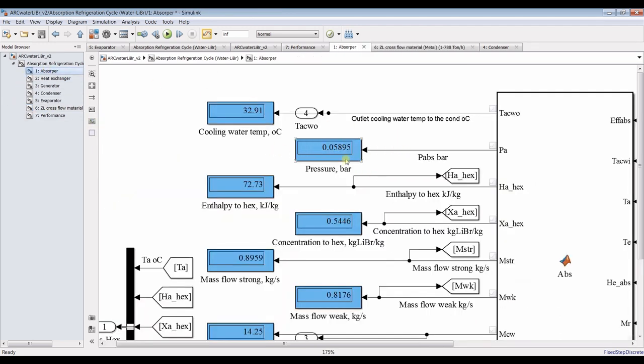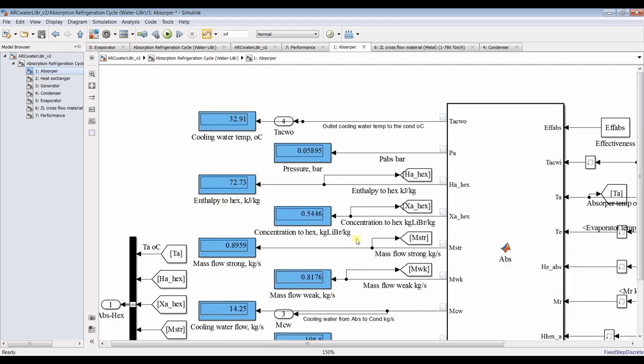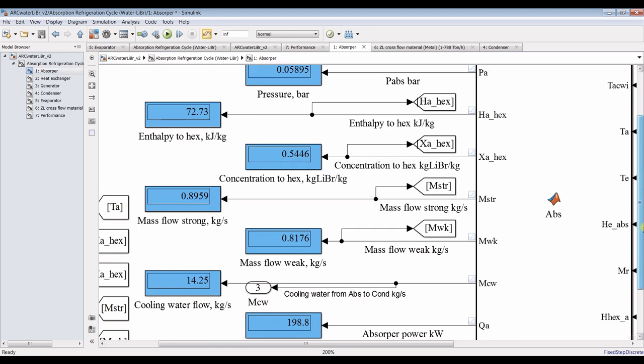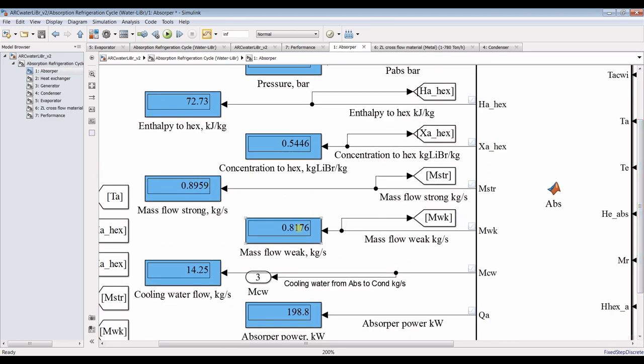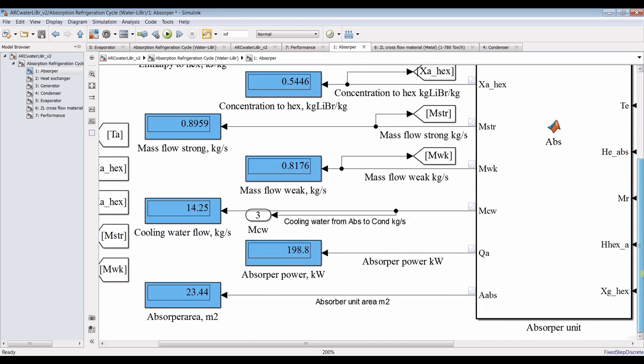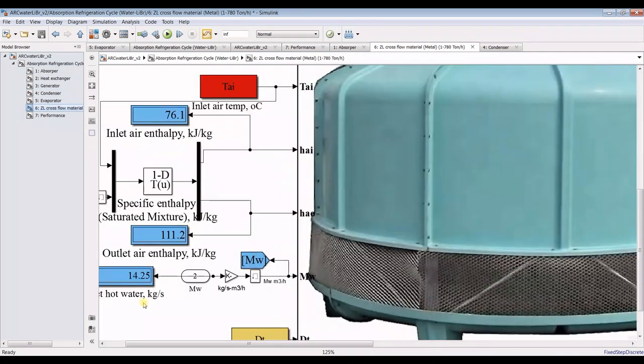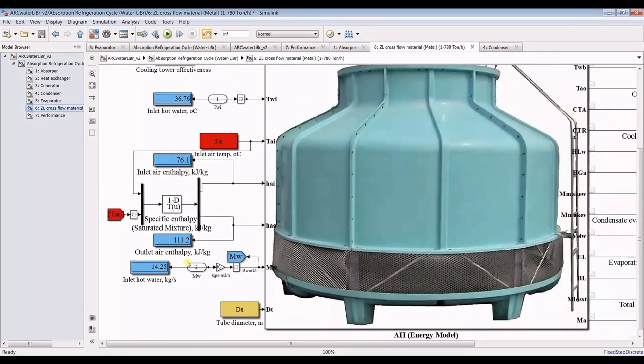For the absorber, we can calculate the pressure and solve the outlet from the absorber: absorber concentration of lithium bromide — in kilograms of lithium bromide per kilogram of total mass flow rate. We have strong mass flow rate of lithium bromide and weak mass flow rate. This is the cooling water from the absorber to the condenser. The total cooling water flow rate by the cooling tower is 14.25 kg/s in order to complete the process.